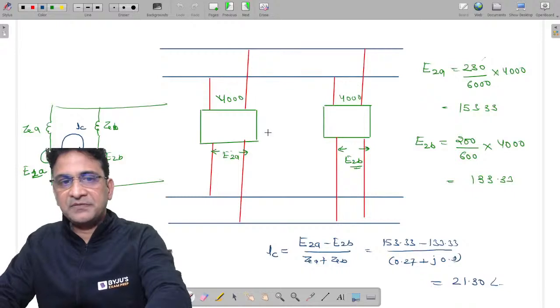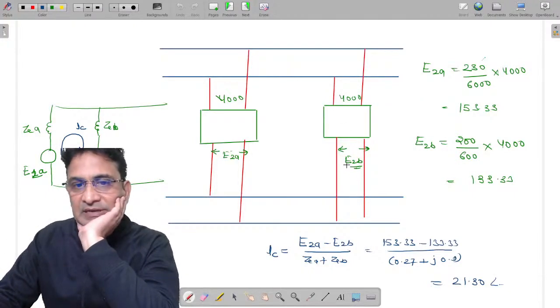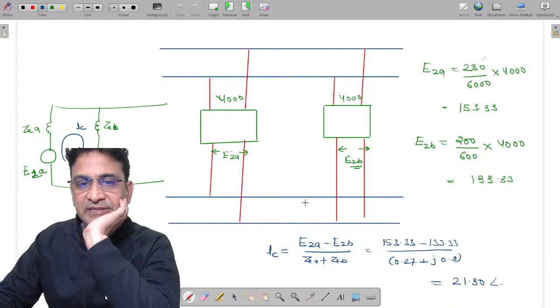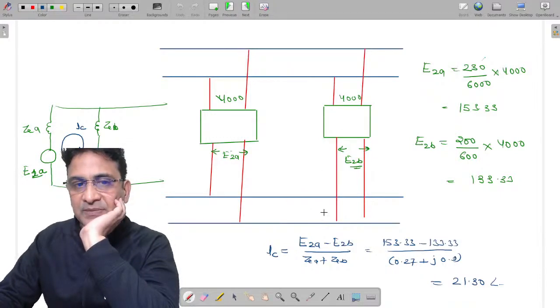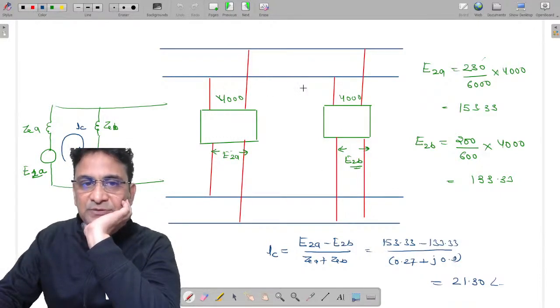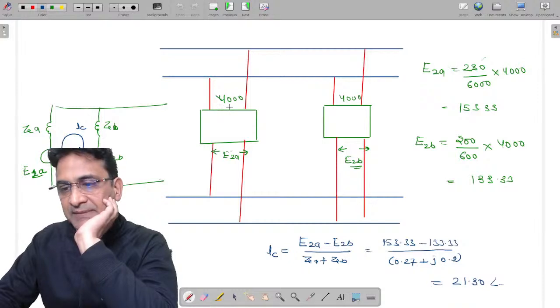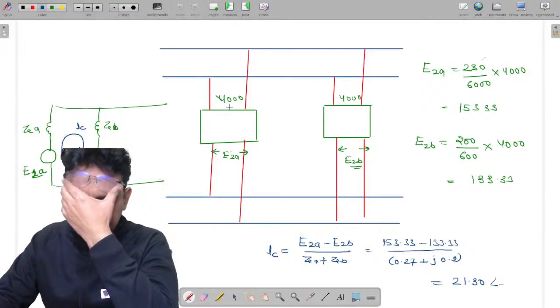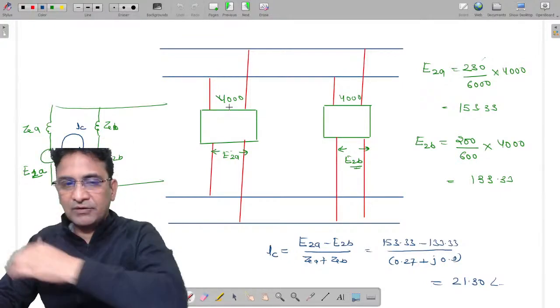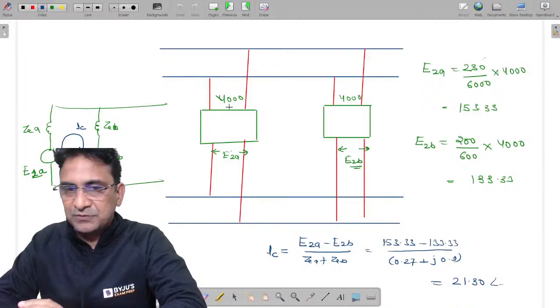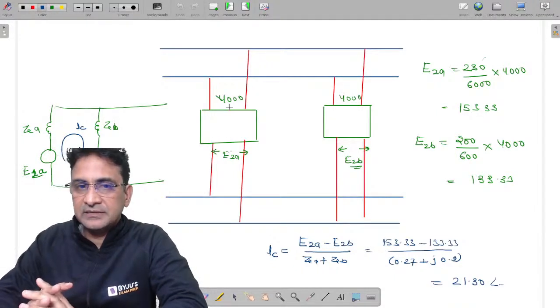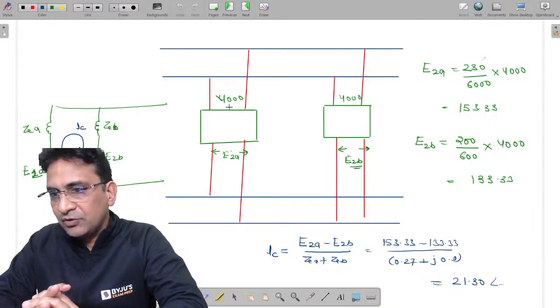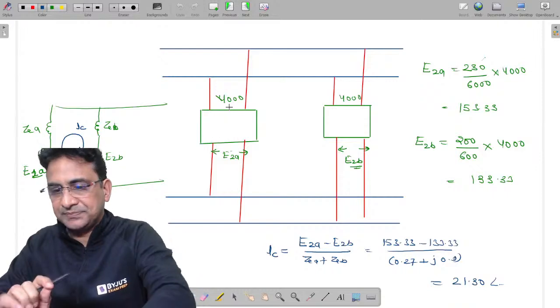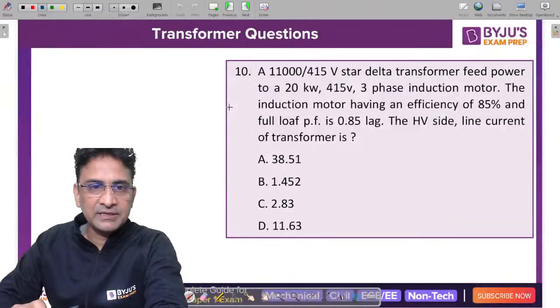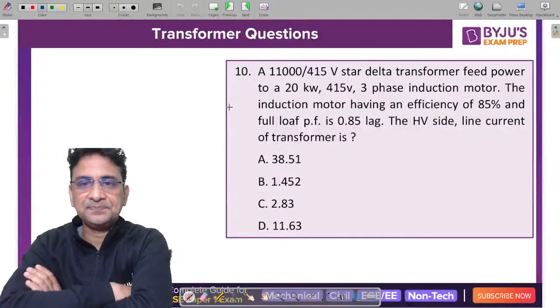Now in the primary winding also the current will flow. Why? Because if the current is flowing in the secondary side of the transformer, then the circulating current also starts flowing in the primary side of the winding. Because the transformer is a device in which you cannot change the current in only a single winding. If you change the current in one winding, the other winding current will automatically change. Okay, come to the next question.